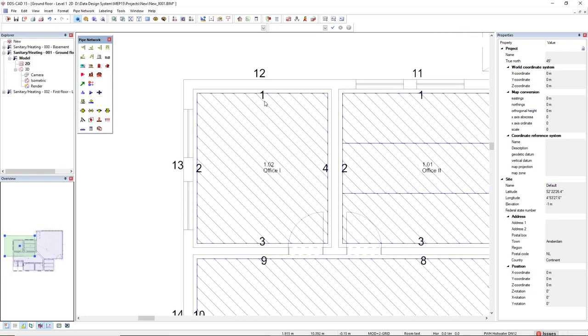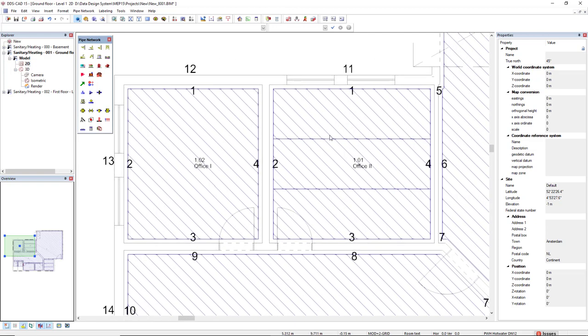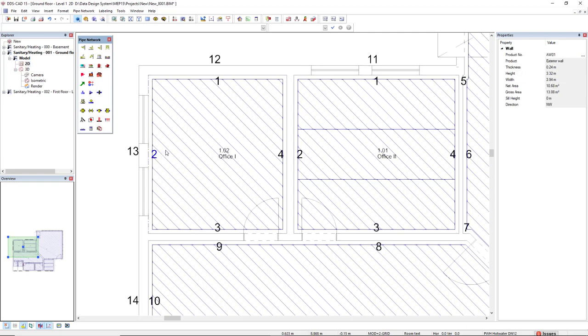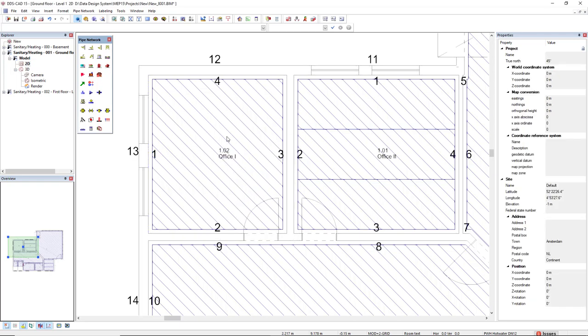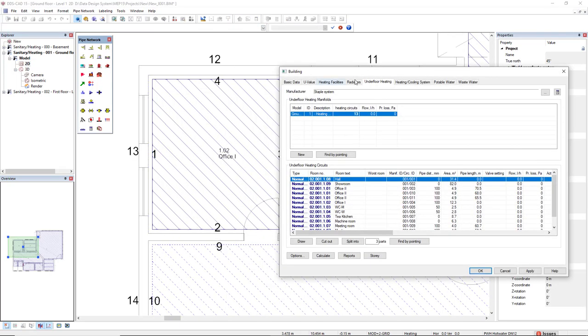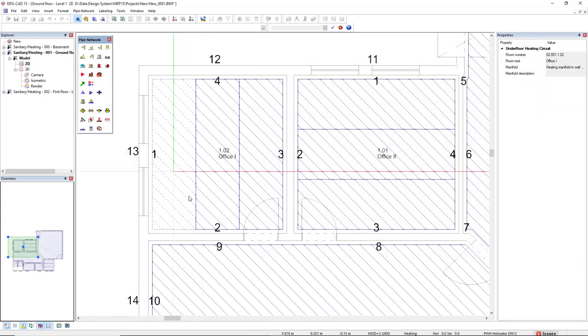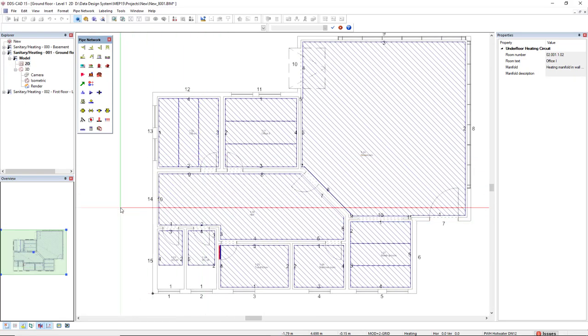because DDS-CAD takes into consideration the wall number. So if I split this room, it would have the same orientation as an adjacent room or the Office II. So what I can do, since I want to have this orientation for these two windows on the left, is select this number 2 in front of this wall, right mouse click, and select the option set wall as first in room. Okay, now I can go back to the building and then to the underfloor heating. If I now split this room, it will get the orientation I'd like to have.